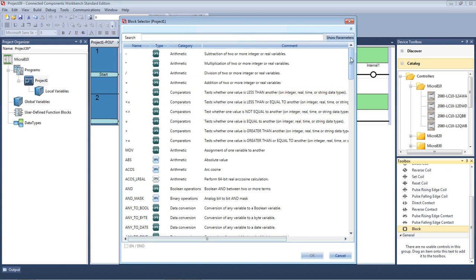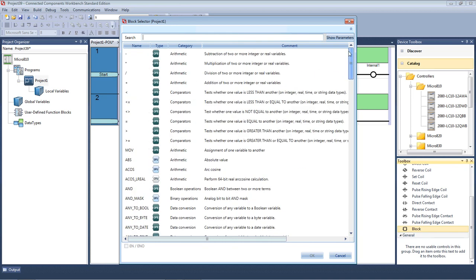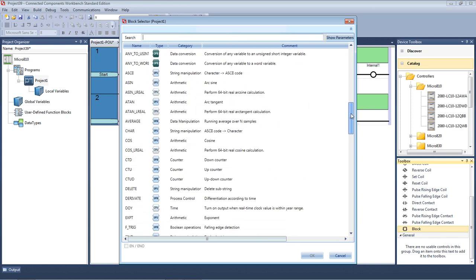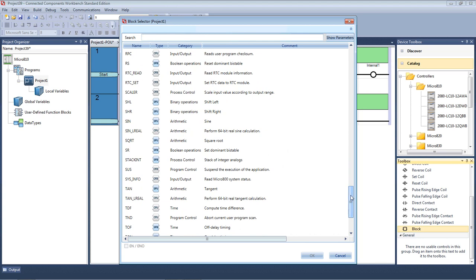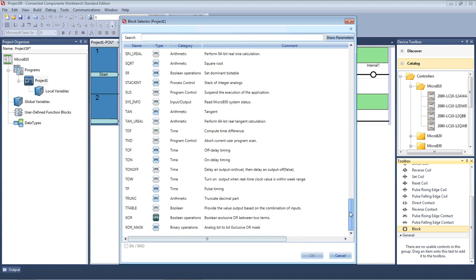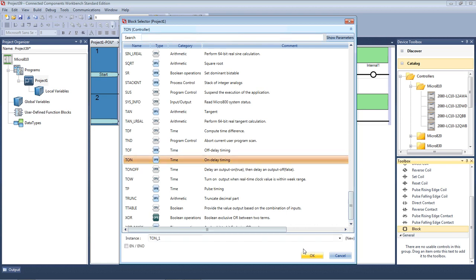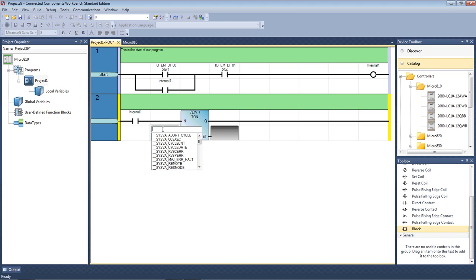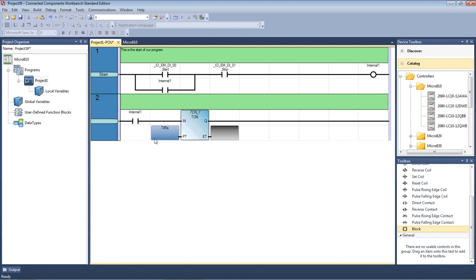What we'll do now is I'll bring a block over. Now, my block, so what I'm going to do now is I'm going to put a timer in. So I'm going to scroll down, and you can see there's a large range of function blocks here. There's a lot of function blocks. Again, you'll need training to actually understand how to use them. So what we're going to look for now is a timer, time on delay. So a simple time on delay timer. So I'll click on that, and go OK. And it gives me a time on delay timer. Now, what I need to do is, I click in this box here, and I need to tell it it's going to be a T for time. I'll put a hash there, and then I say, OK, I'll give it, say, five seconds. Now, five S is five seconds. If I put an M in there, it's minutes. H for hours, and so forth.